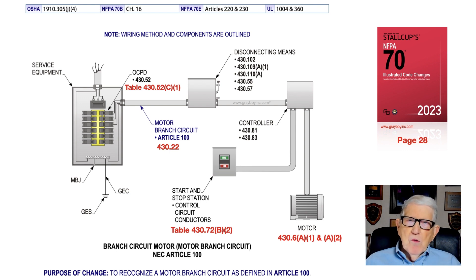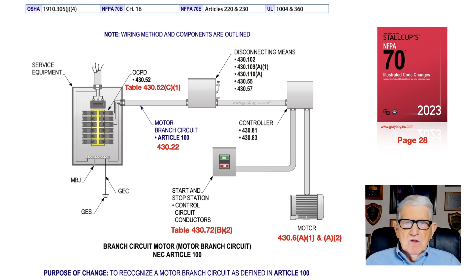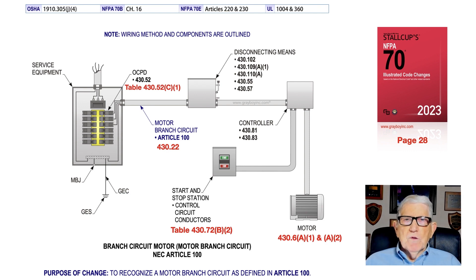You have the disconnecting means with its appropriate sections for the controller and the motor. At the controller, you have your different sections where you could look up more information. You have the stop and start stations or the controlling means in accordance with Table 430.72(B)(2). Then, of course, the motor itself — nameplate ratings, table current values — listed in 430.6 A1 and A2. For the starting method used for the motor, see 430.7B. This definition will be a very helpful, usable term in Article 430.